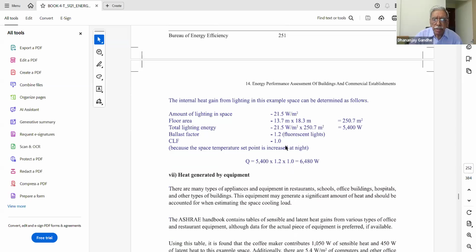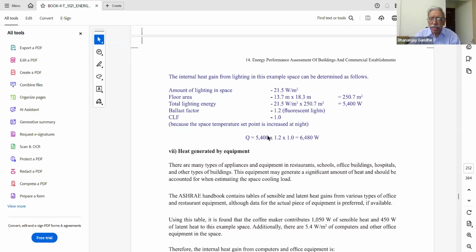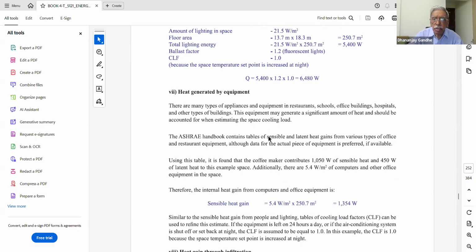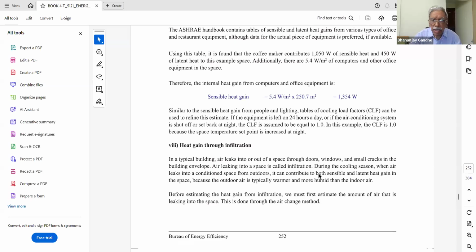Okay, so this way we can calculate the lighting load. Now sometimes the lighting load may not be specified in terms of the total watts for each lighting fixture, but it may be given as a lighting power density, in which case you have to multiply that lighting power density by the floor area to get the total lighting load. So that is the total wattage of the load multiplied by ballast factor and CLF. That gives you the total heat that is generated and imparted to the space by lighting. Okay. So also the equipment, of course, you'll have to know the total kilowatts, the office equipment load, printer load, and any other load, any coffee maker, tea maker, etc. You have to add those loads in terms of watts. Okay. So that gives it a total wattage.